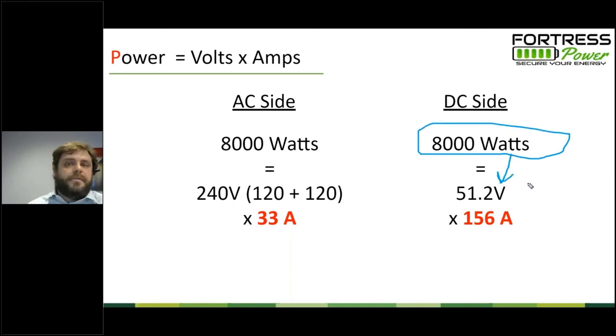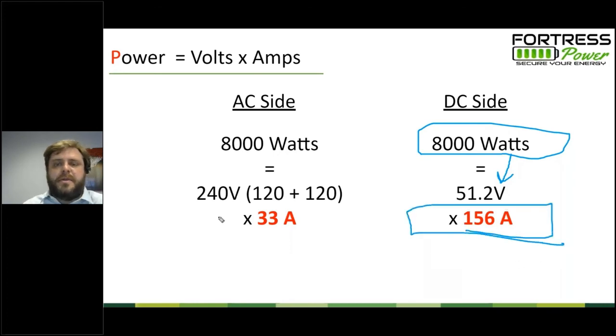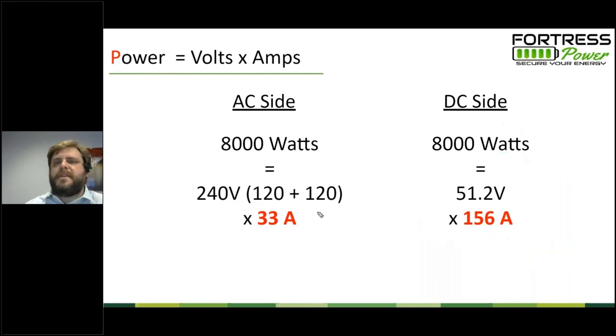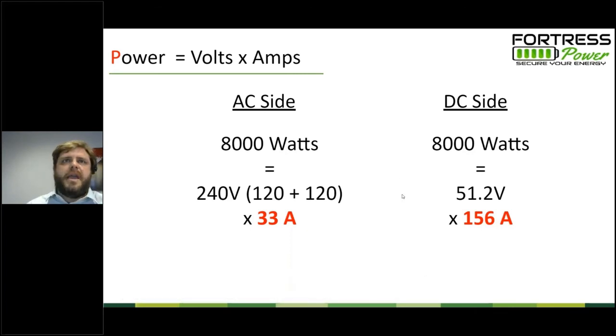I'm dividing by the nominal voltage of my battery bank, and that gets me to my continuous output amperage capacity. And again, just to repeat, the big surprise here is that low voltage DC battery banks run at high amperage. The grid is relatively higher voltage, 240 volts versus 50, and so the AC output of the inverter is going to have a much lower amperage than the DC side input. And we're going to talk about that a little bit more when it comes to DC combining towards the end of the hour.